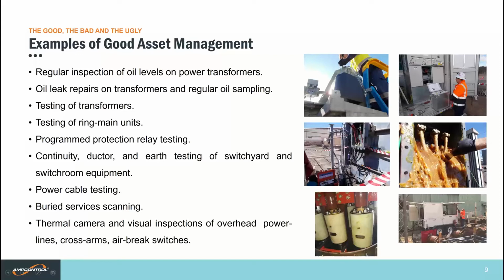A couple of the photos that we have up there. We have some topping up of transformers, which is quite common. If there's a lot of leaks on the transformer, then your oil level will drop. And as we all know, it can be affected by the temperature. If it's a cold day, the oil will contract, which can cause tripping. Second one there to the side is some high voltage testing on 33 kV switchboards.